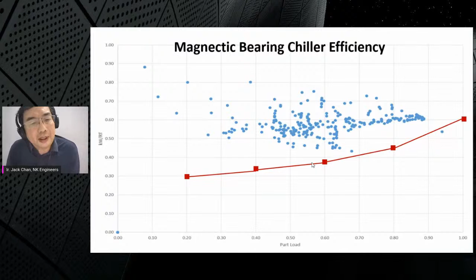As owner, you have to maintain the site condition, like the chiller. You have to clean it, because once the chiller operates for a while, the coil will get dirty. The approach temperature will increase, meaning the temperature of the refrigerant against the chilled water temperature will increase. Fouling will happen, the tubes will get dirty, and you won't get the efficiency anymore.